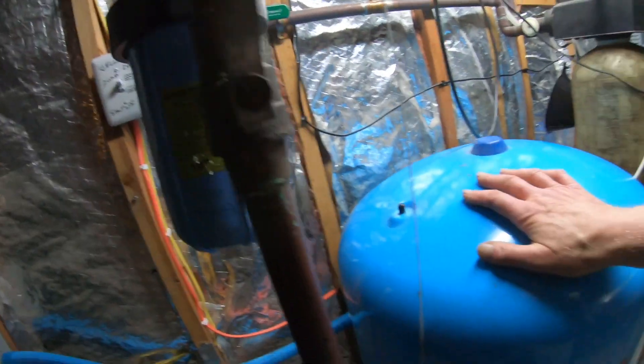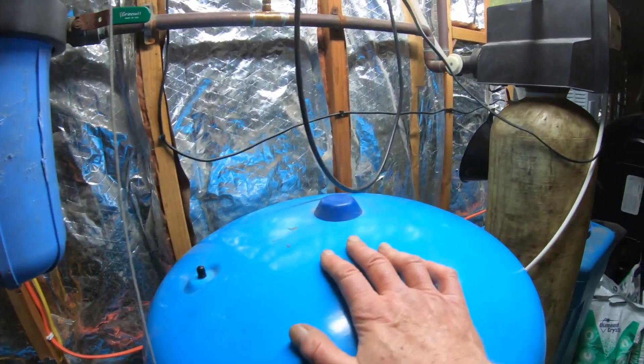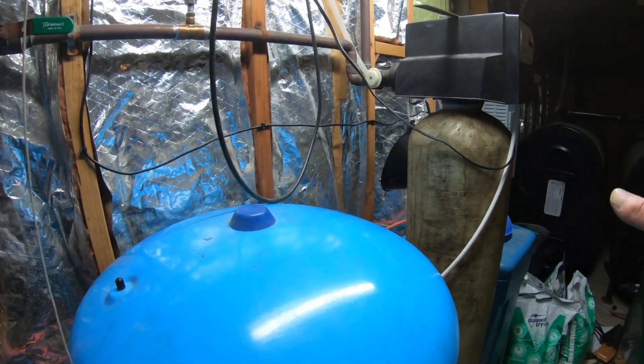The pressure in here when the tank is empty is supposed to be 70% of 68. So 70% of 68 is about 48 PSI. I calculated it and I believe it's 48.